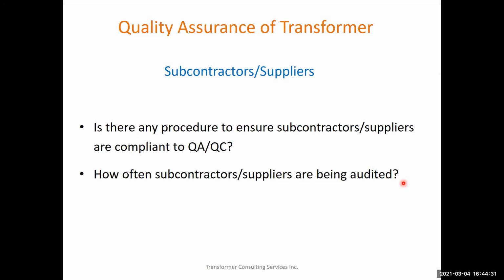Besides that, consider how they manage subcontractors and control their quality. Two things I've seen around the world that can compromise transformer quality: first, the tank. Most manufacturers no longer build the tank in-house; they outsource it to a third party, and when they do, quality isn't always maintained. So when the transformer goes to site, one common failure we see lately is the tank leaking or even rupturing, especially leaking. I can show some pictures on that if we have time.